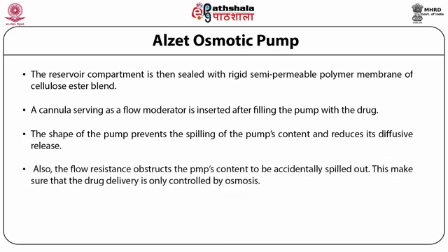The shape of the pump prevents the spilling of the pump's content and reduces its diffusive release. Also, the flow resistance prevents the pump's content from being accidentally spilled out. This makes sure that the drug delivery is only controlled by osmosis.